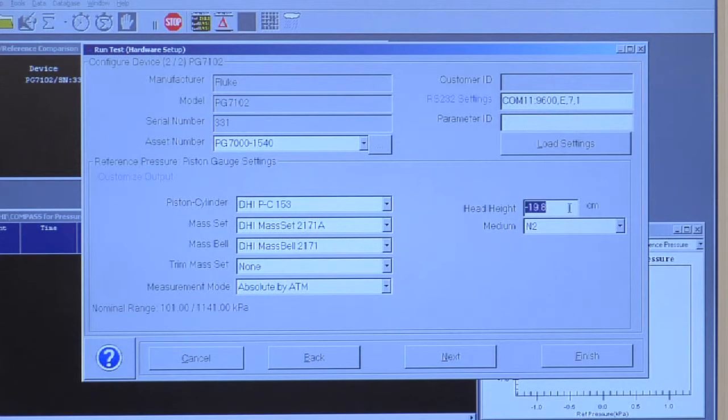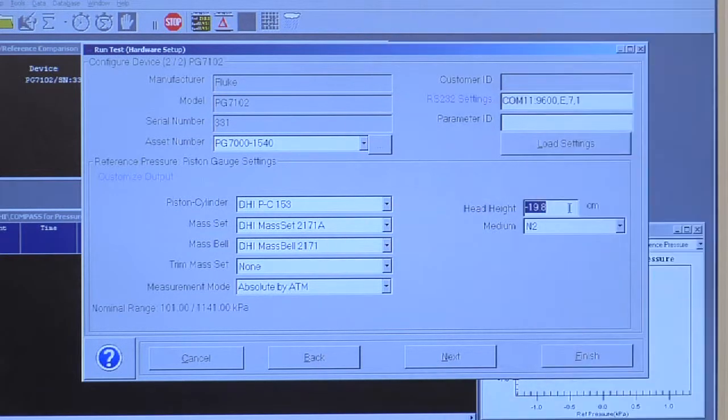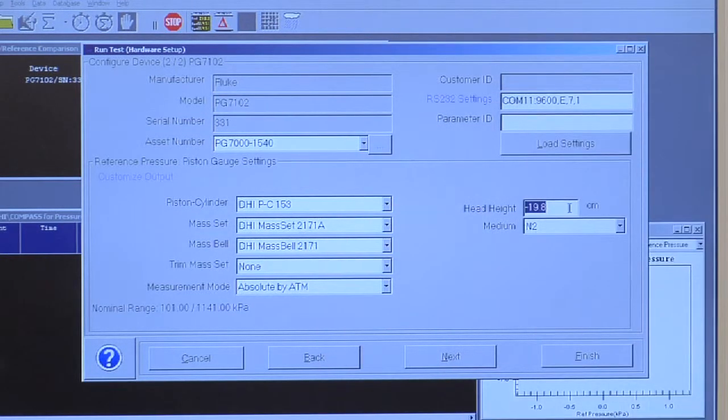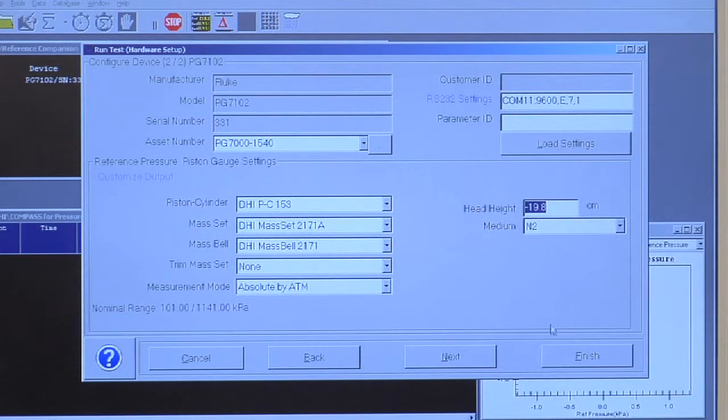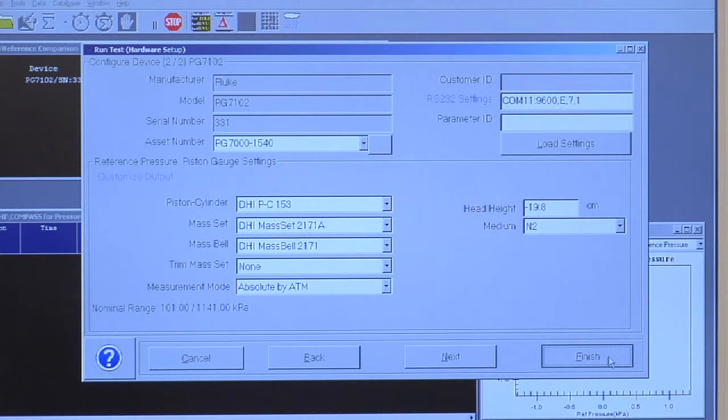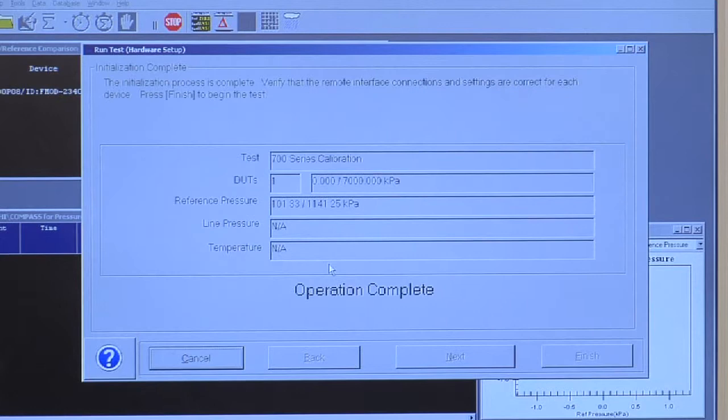This is the head correction. That defines the change in height between the reference level of the piston gauge and my device under test. Now I can choose finish. This will go into the runtime of the test.